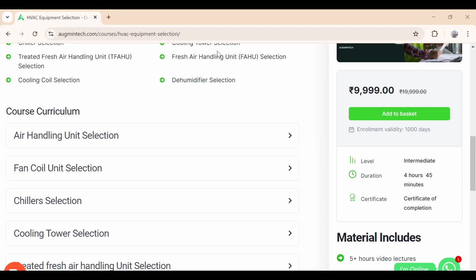Actually, remember for fresh air, I have already explained how you will get the exact value. You're talking about thumb rule versus exact calculation. We have a formula. The fresh air calculation formula I have already explained: CFM per person into number of people plus CFM per square feet into area. Once you get the fresh air and the supply CFM from the heat load calculation, you can calculate the return air. Supply minus fresh air is your return air CFM.